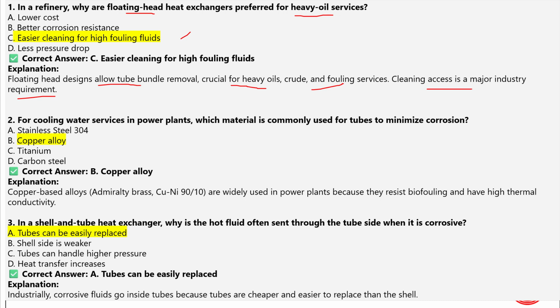Next question is, for cooling water services in power plants, which material is commonly used for tubes to minimize corrosion? So the answer is copper alloy. So why copper alloy? Copper based alloys, namely brass and Cu 90 Ni 10, are widely used in power plants. Why? Because they resist biofouling and have good thermal conductivity. So that's why, in preference to other materials, the copper alloy is used.